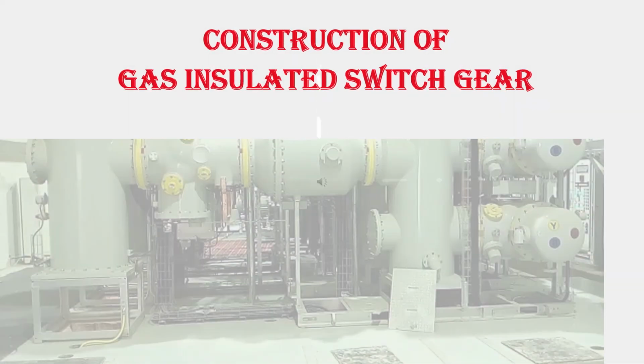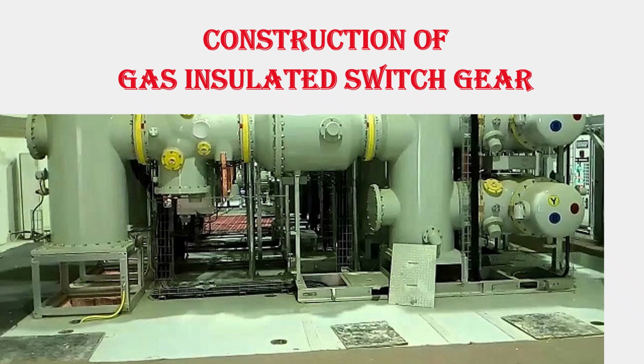Base assembly shall consist of separate modular compartments like circuit breaker compartment, bus bar compartment filled with SF6 gas and separated by gas tight partitions. The maintenance on one feeder shall be possible without de-energizing the adjacent feeder. Accessories like particle trap, pressure release devices, desiccant, etc. shall be provided for each compartment.